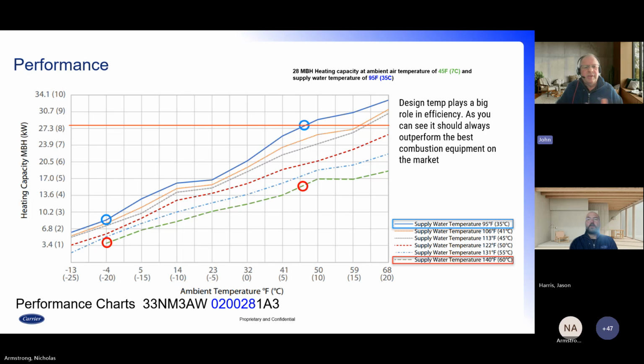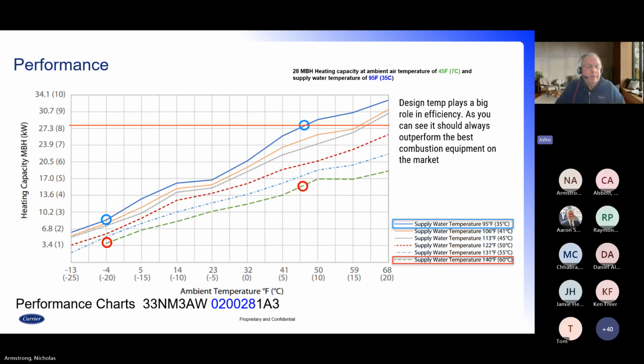But in this particular sense, now we're losing the output on the heat pump here with that bottom green line. So that represents the 140 degree, which is the maximum temperature output of the heat pump. And you can see that at that point there, we're probably roughly half of the output because of the higher temperatures.